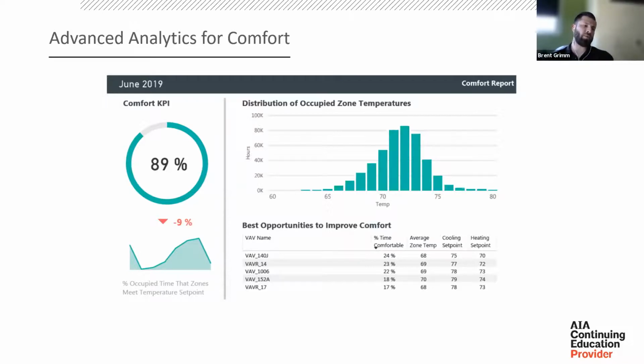Also in the table, you'll see we've got that key performance indicator, the percent of time that they're comfortable. So the lower that number, the worse. And then we provide some other context next to it so that the operator has a little bit of an idea of what to look for. So when we see a 68 degree average zone air temperature and a heating set point of 73, we know there's probably something going on with a hot water coil there, and we can start looking at that pretty quickly.